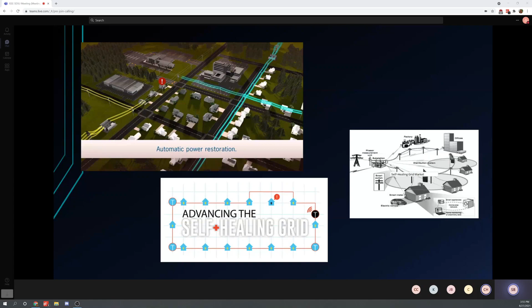So we have things called reclosers that, when the power goes off, will trip and then close back in to see if there's still an issue. If there isn't, great. You might see momentary outages where power goes out for 5 or maybe 45 seconds, then bam, you're back on, and you think, that was weird. Or maybe you never noticed because it was in the middle of the night. That's because we have these automated functions that let the system heal itself. That's a really cool area, and there's a whole lot that goes into it.